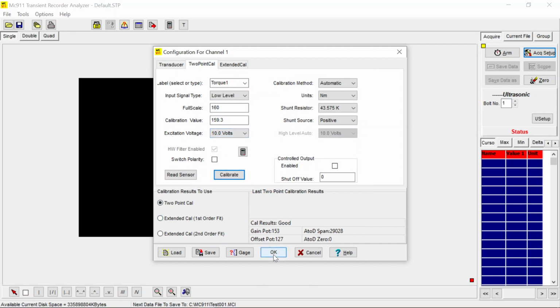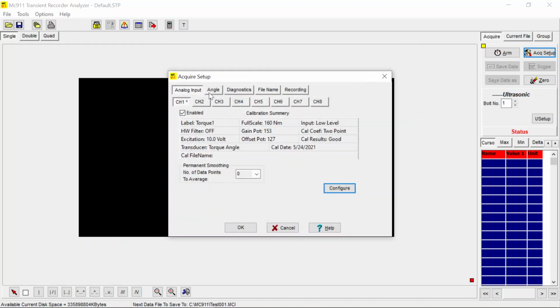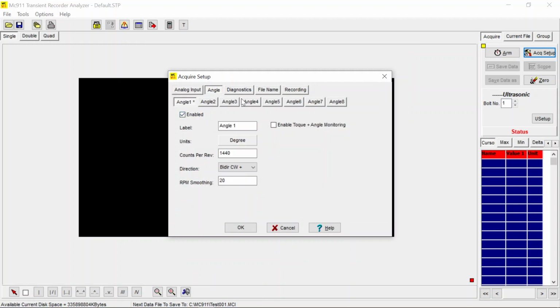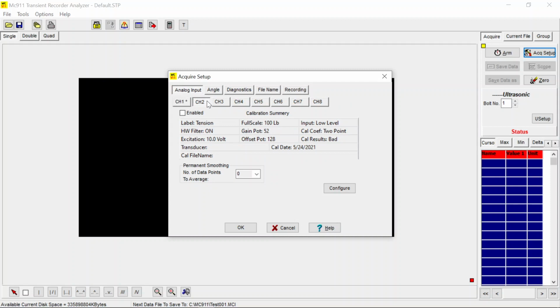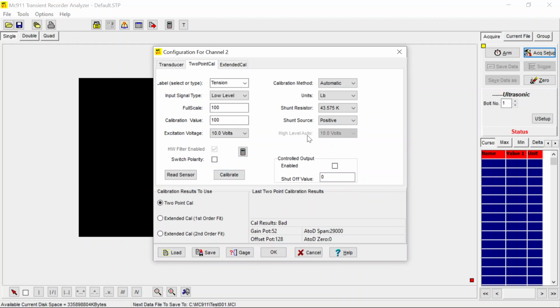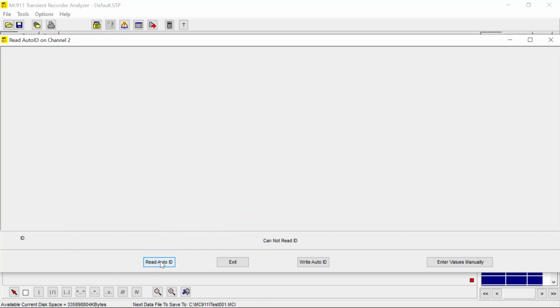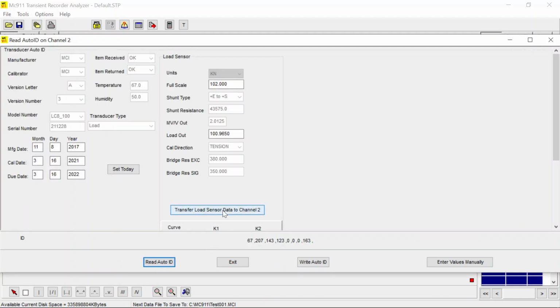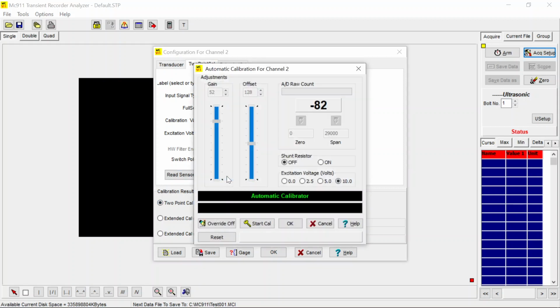Okay, and let's go. Make sure angle is enabled and go back. And channel 2, we can enable our channel 2, which is our load data. It's called tension here, and the label is tension. So let's read the data. Click again, read the data, transfer, calibrate, start cal. Same again, it shows you close to 0 and close to 30,000 for the load cell as well.